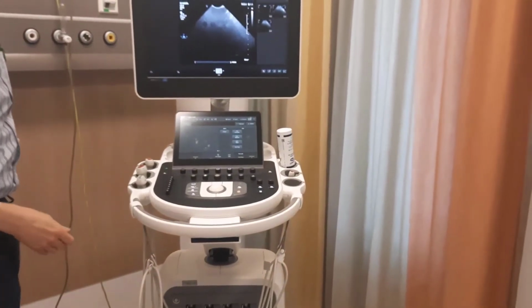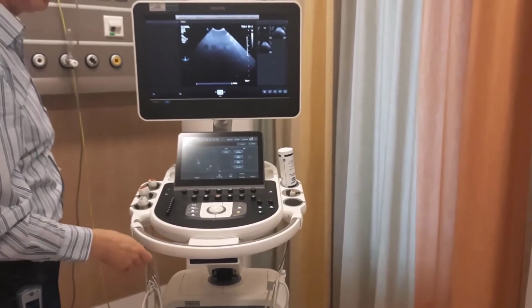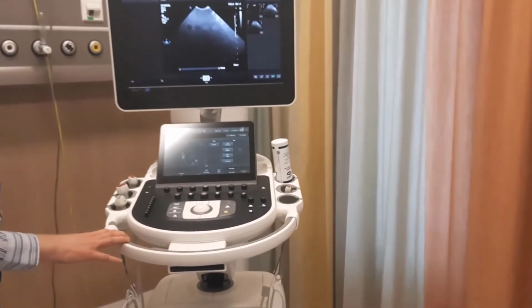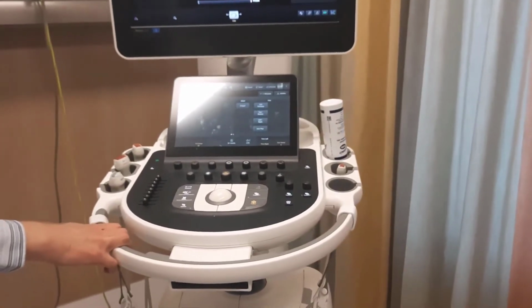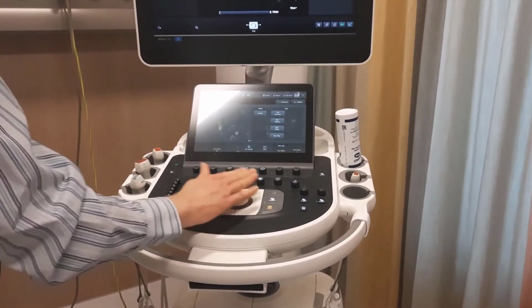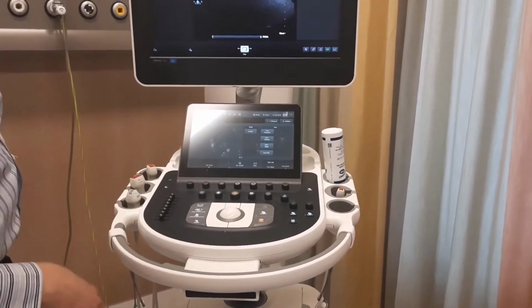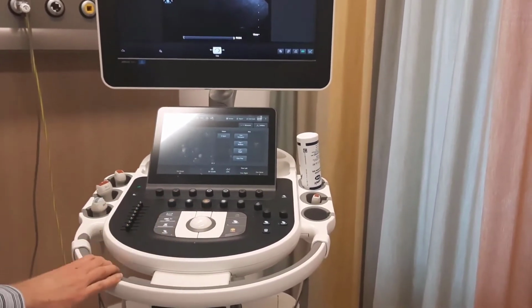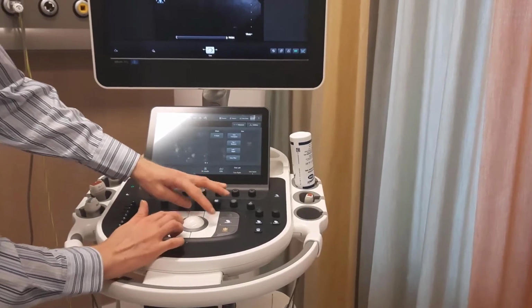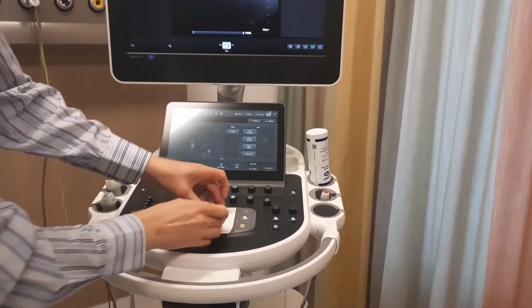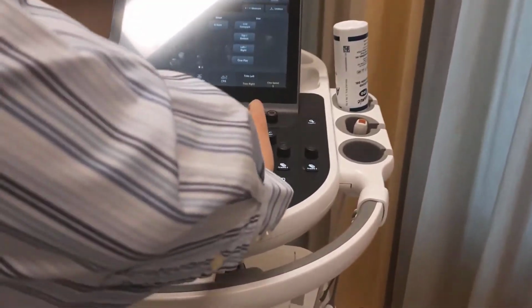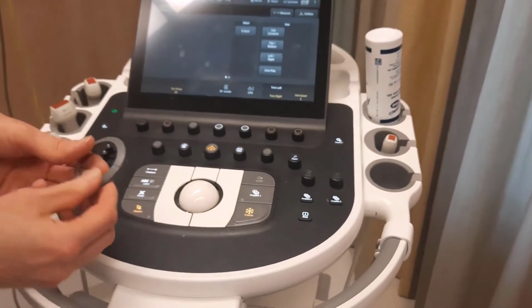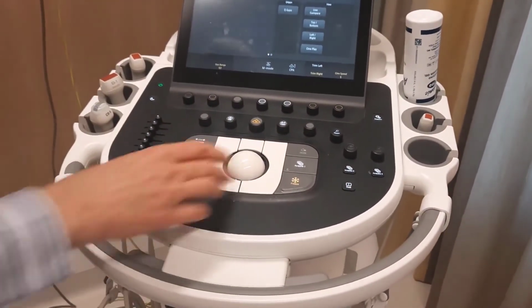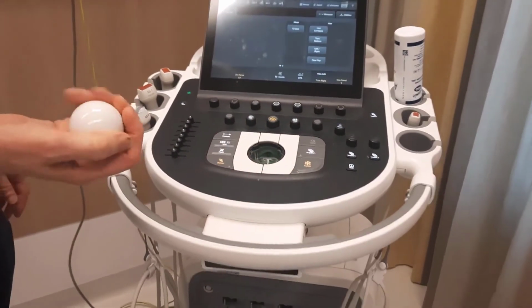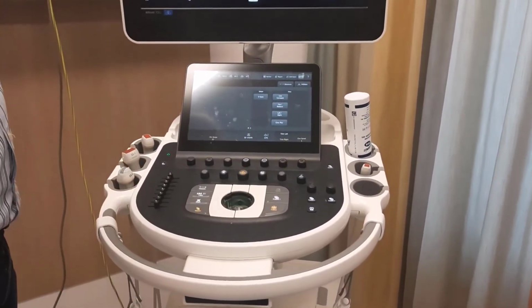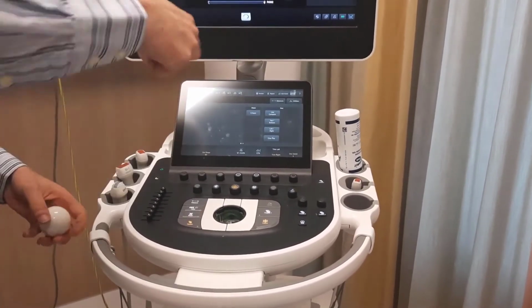Another thing that every ultrasound needs attention once a year is the trackball. People working with ultrasound use a lot of gel, and they have to use the trackball to select options in the menu. So the trackball can get dirty. On almost every machine you can remove the trackball by turning this ring counterclockwise. Pull the trackball out. That's sometimes difficult because it's very flat. Then you can use a bit of tape and you can easily pull it out.